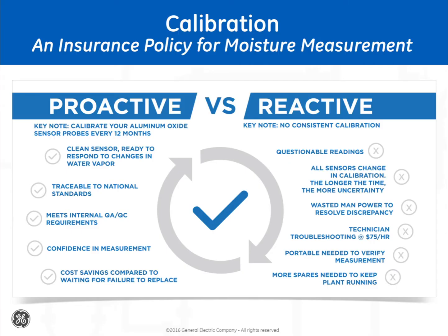Think of calibration as an insurance policy for your moisture measurement, not just a good habit for your sensors. Proactive calibrations instill confidence in the measurements and in the processes that these measurements enable. Reactive calibrations are typically initiated when the operator is questioning the sensor readings. This is not a good starting point for any investigation. It is easier to blame the sensor as opposed to the measurement system or the process.